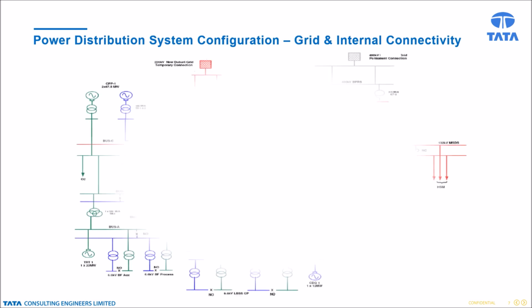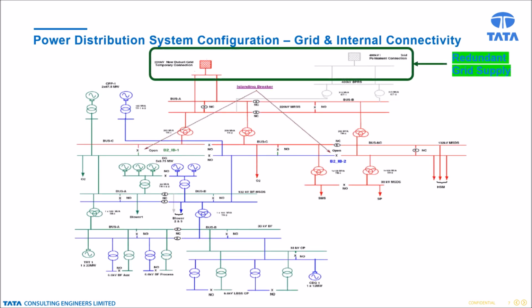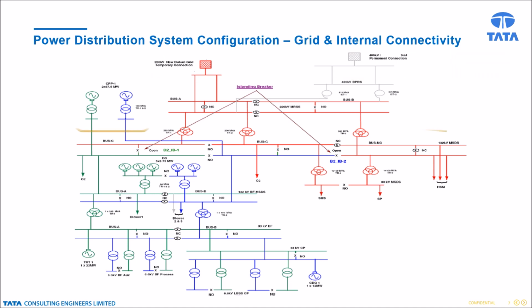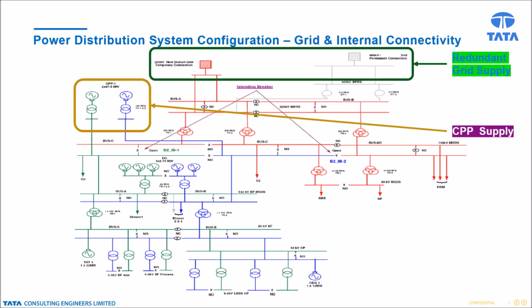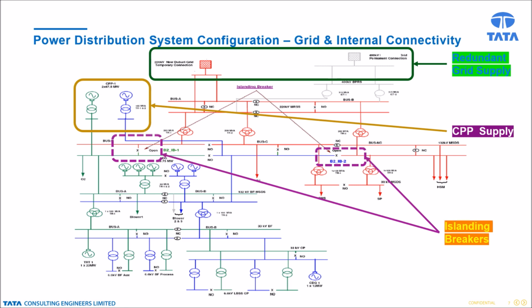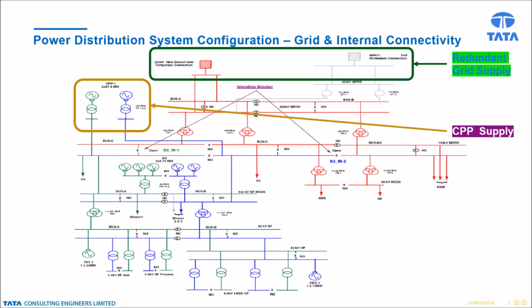A typical power distribution system is shown depicting the connectivity of utility grid and captive power plant generators. The primary power distribution system should be arranged such that critical and non-critical loads can be operated at different islands. Power supply to critical loads are made from a bus section where grid and captive power generators are connected. It is observed that grid power and captive power are connected at 220 kV and 132 kV bus respectively. Under normal operation of power system, grid and captive power generators will be running in parallel at 132 kV bus with bus coupler breaker B2IB1 and bus section breaker B2IB2 closed condition.